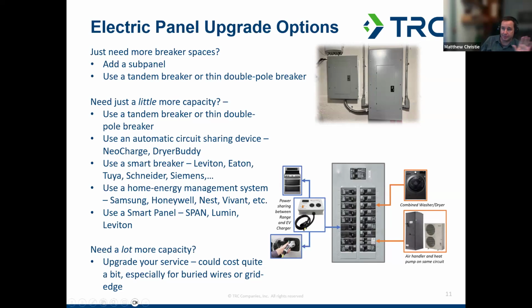Close means 80 amps. That's the threshold. If you're on 100 amp service, 80 amps is the most you can ever pull coincident before being dangerous. So we do the math on that spreadsheet, it adds up, it says alright, you're close, you might. But then you actually operate the house, and it's like, it said I might get to 80 amps, but that has literally never happened. I didn't even get near that. I got to 10 amps, 15 amps as the max of an entire year. Why do I need a service upgrade to 200 just because I'm adding like a 30 or 40 amp EV charger? I'm never going to get there. I know your math is telling me that I will, but I won't.